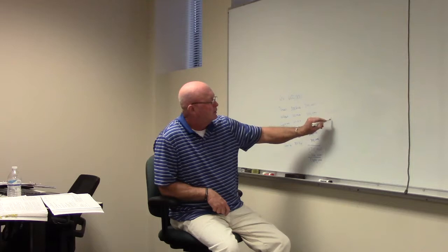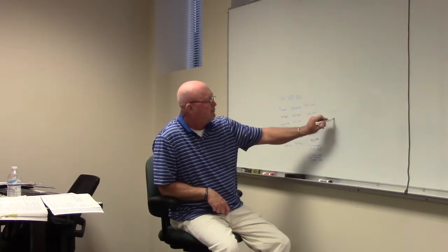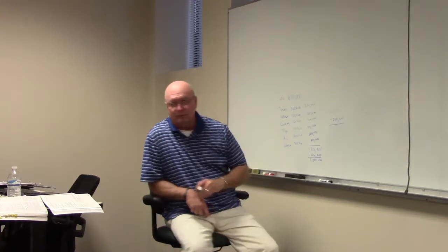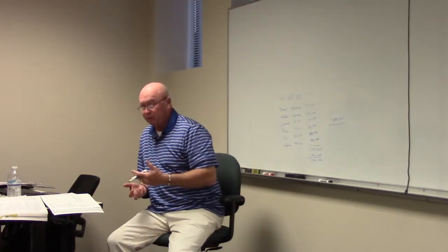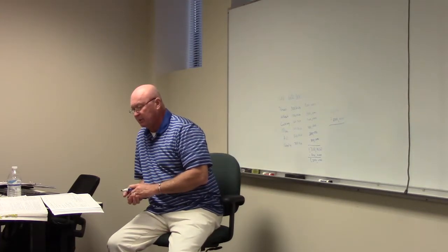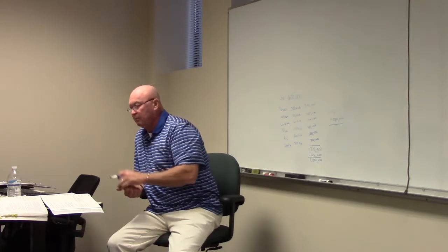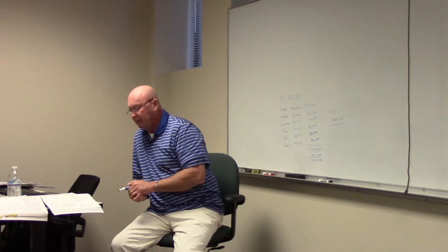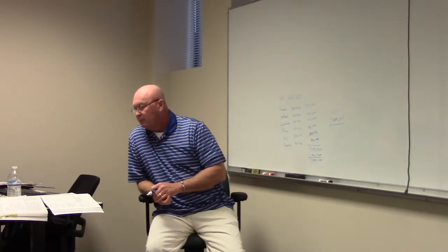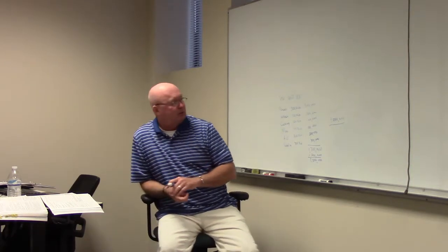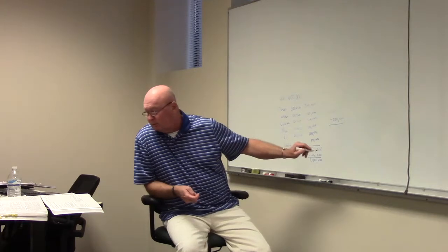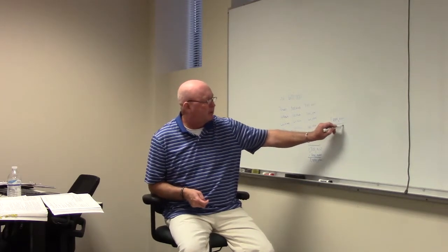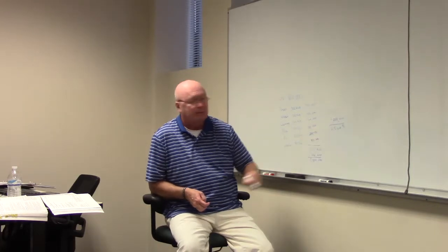So we got 1.5 million divided by 200,000 is equal to, we're going to find how many volt amps per square foot we actually are doing, because that's what our actual table tells us to do. So how much is this equal to? 7.5 volt amps per square foot, right?